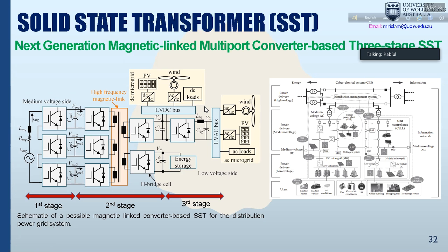That sensor can sense how much current is flowing. If it looks abnormal, we can just remove the gate pulses from the IGBTs, and then it is turned off. Current cannot flow through these devices, it is just disconnected. We don't need any isolator breaker like what we use in the existing or traditional grid or network.